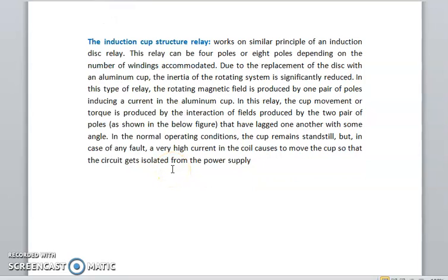The induction cup structure works on a similar principle to an induction disk relay. This relay can be 4 poles or 8 poles depending on the number of windings accommodated. Due to the replacement of the disk with an aluminum cup, the inertia of the rotating system is significantly reduced in this type of relay. The rotating magnetic field is produced by one pair of poles inducing a current in the aluminum cup. In this relay, the cup movement or torque is produced by the interaction of fields produced by the two pairs of poles that lag one another by some angle.